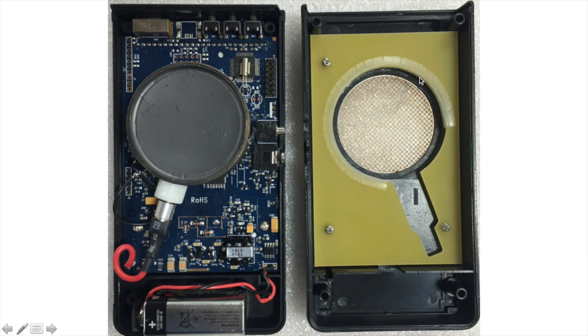If we open the detector, this is what you see. Again, this is looking from the back. So that's the mica window right there. That's the GM tube. This type of tube is called pancake GM tube, kind of looks like a pancake. That's the grid on the back of the box. Then you can see the anode connecting to the high voltage, and the cathode is right here connecting to the ground through a resistor. You can see the switches on the top.